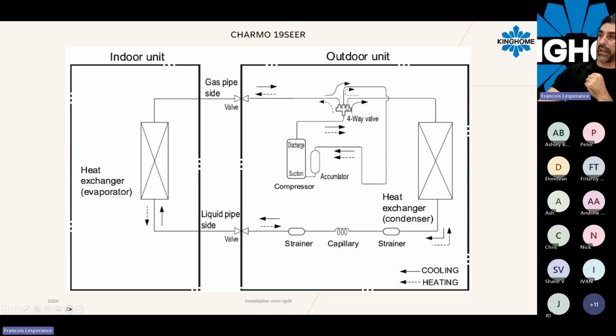There's a U-bend, and the tube in the middle of the four-way valve is always a through suction line. So this part here going back to the compressor is always a through suction line. We will pass by an accumulator right here. The accumulator is a small cylinder stuck to the compressor shell. It's here to protect the compressor, to avoid liquid strike at the base of the compressor. We are using a twin rotary compressor for every system, so any kind of liquid inside that base will damage the compressor for sure.